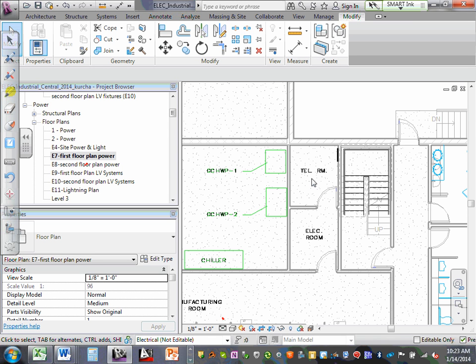And what does that mean? That means that sensor, this happens to be a heat detector, okay? That sensor has its own address in the fire alarm system, and is annunciated at the control panel as heat detector in room whatever. It's got a chip in it, and it talks to the control panel, can interrogate that device, and depending on whose system you're selecting, what the technology is available, you can even potentially interrogate it to know what the temperature is inside the room. Is a real-time analog signal. But we're not going to go to that extent.